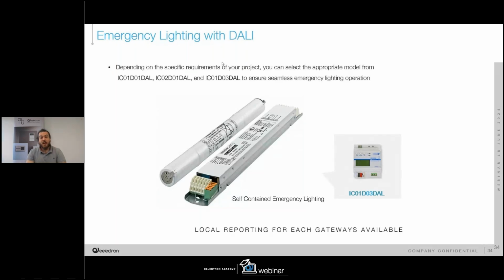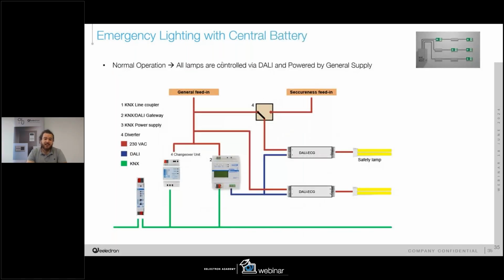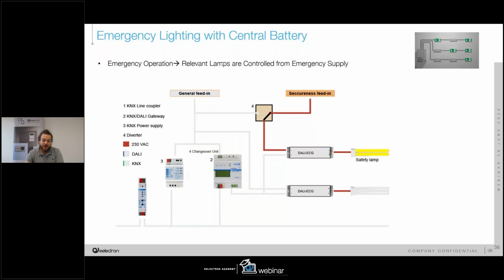Another kind of emergency lighting system, as said, is the central battery, so with the central UPS, and in this case we can use any kind of ballast without any problem, because the test is performed by the BMS. In this example, we can see how the DALI system is working fine when the mains is okay. But if the mains voltage drops, the battery starts to feed every emergency lighting system, and thanks to our gateway, we can keep track of what happened and manage this.